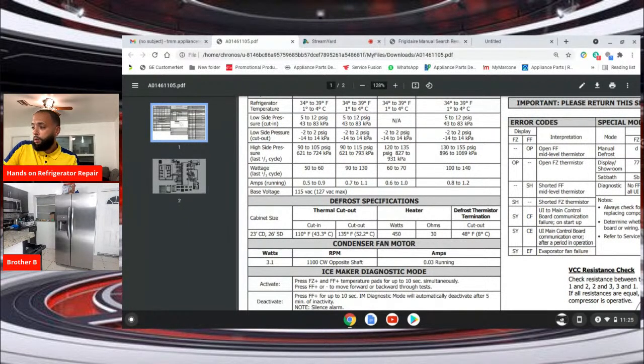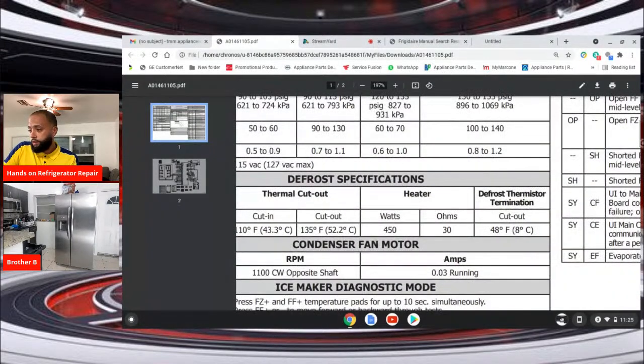Look at that, 0.03 running, wow. So even if you have a condenser fan motor that's in question, let's say it's weak or you have to use your finger to spin it. If you have a clamp meter, you can take an amp reading on this, and look, it even tells you 0.03.